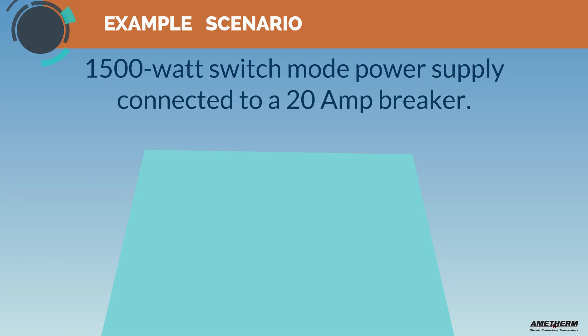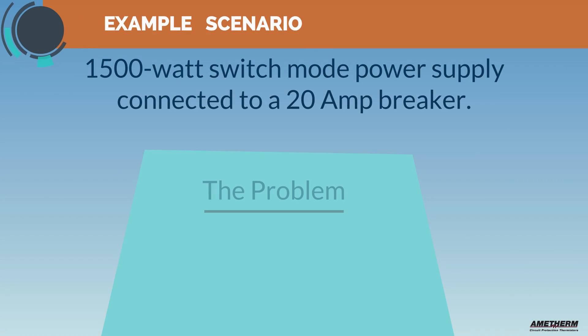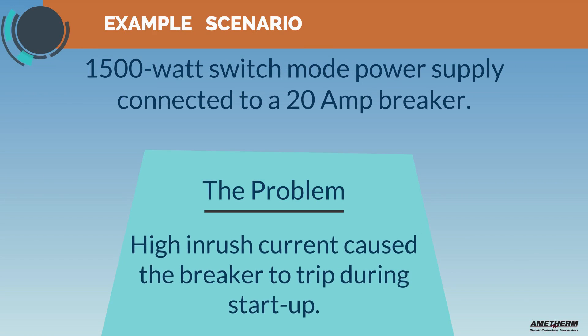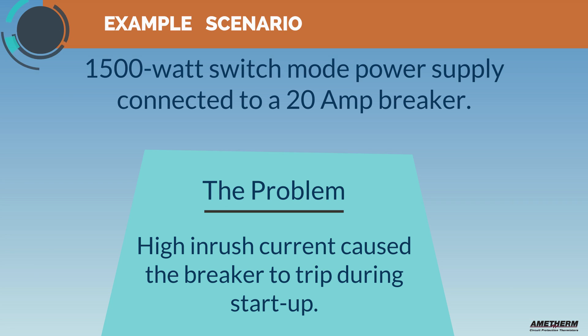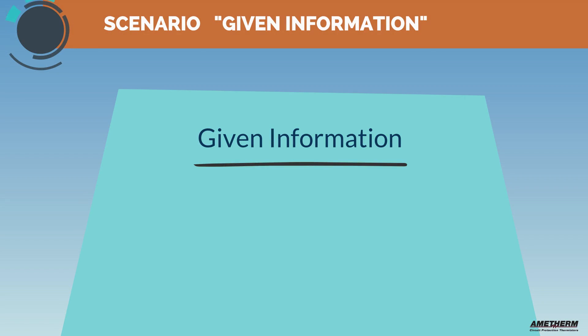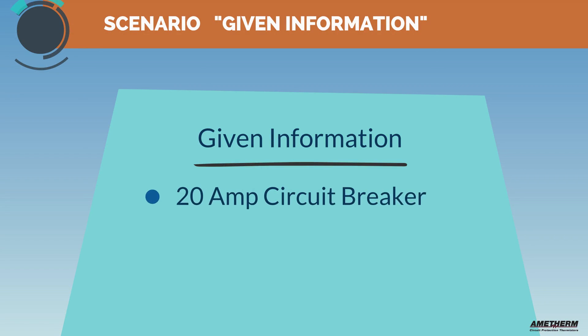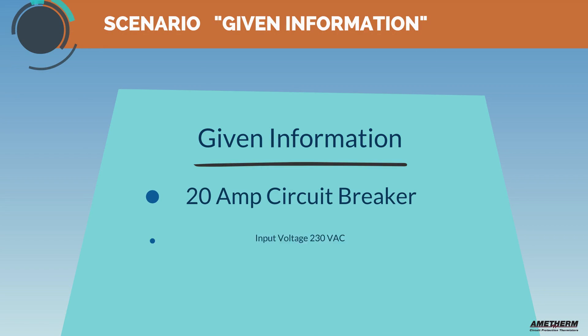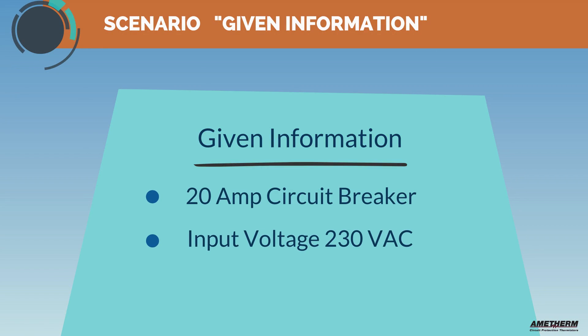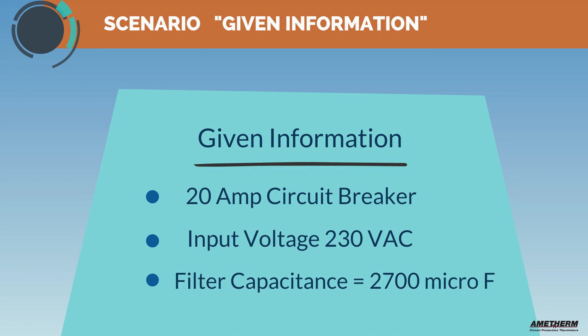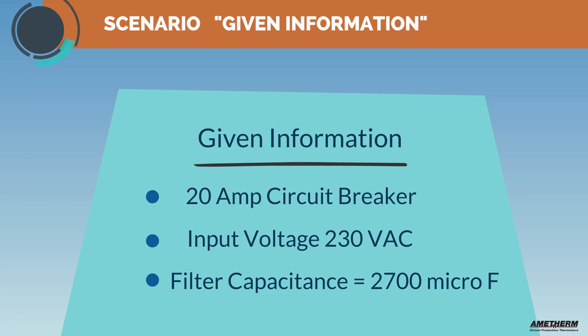In this scenario, our customer was using a 1500 watt switch mode power supply connected to a 20 amp breaker. The problem? High inrush current caused the breaker to continually trip during startup. The given information in this scenario is a 20 amp circuit breaker, 230 VAC input voltage, and filter capacitance of 2700 microfarads.